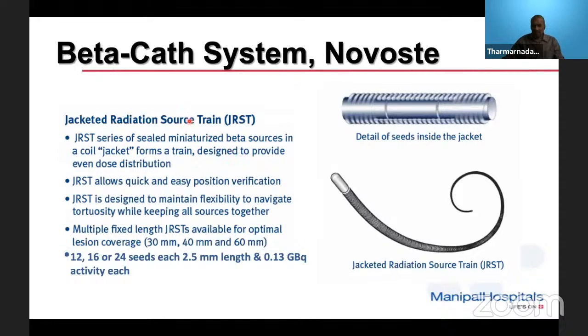The source is made of a jacketed radiation source train called JRST. The JRST is a series of sealed miniaturized beta sources in a coil or jacketed train, designed to provide even dose distribution. This type of arrangement allows quick and easy positioning, and we can also verify whether the source has been positioned correctly or not. It is designed to maintain flexibility to navigate even very sharp turns while keeping all the sources together. Multiple fixed lengths are available for optimal lesion coverage: a 30 device, a 40 device, and a 60 device.